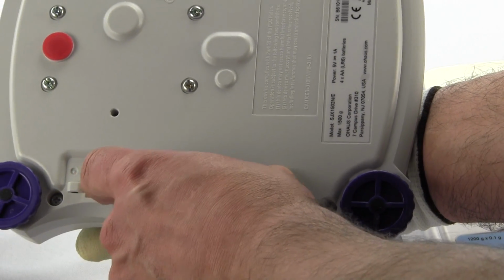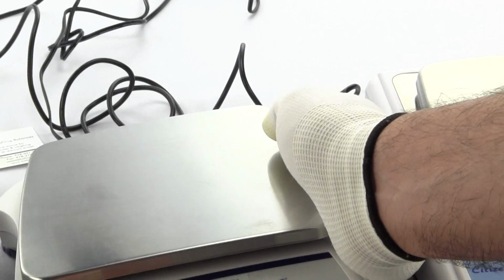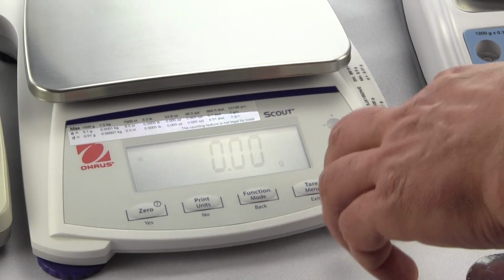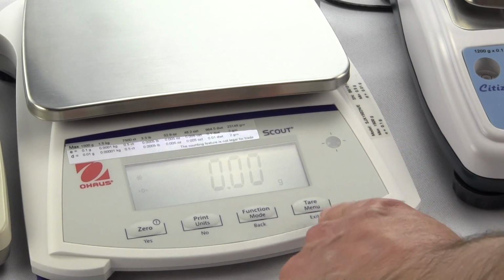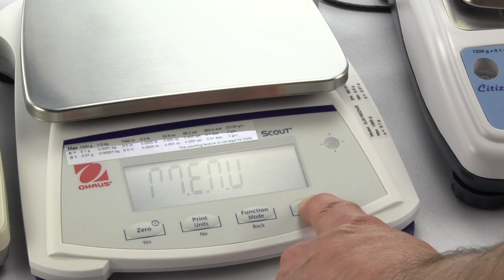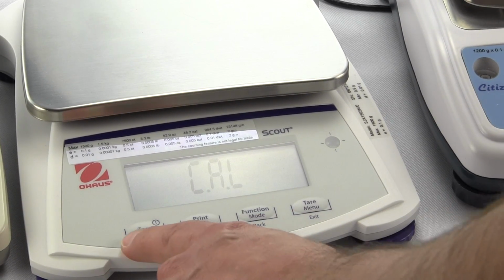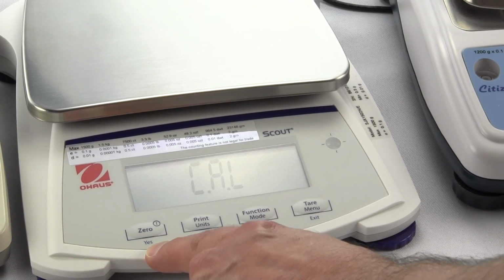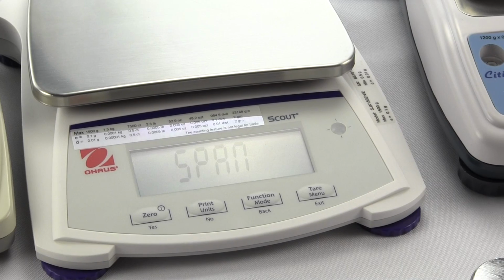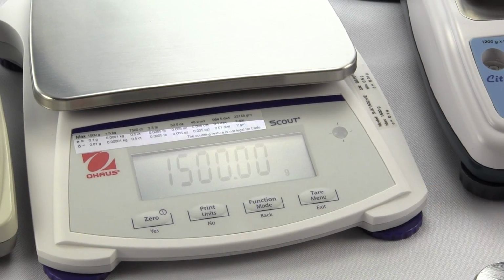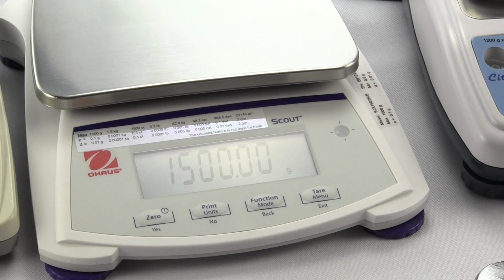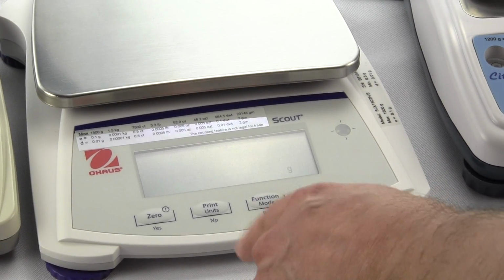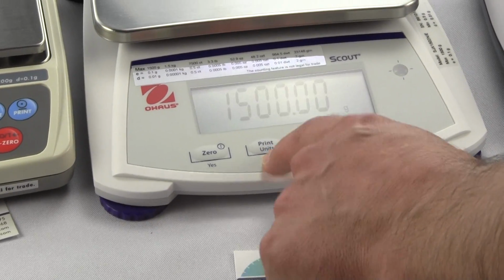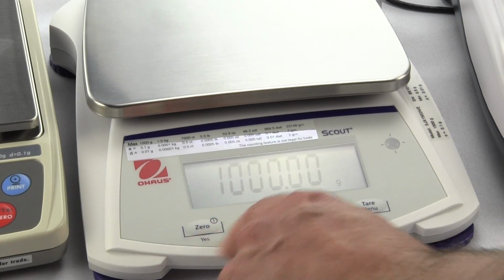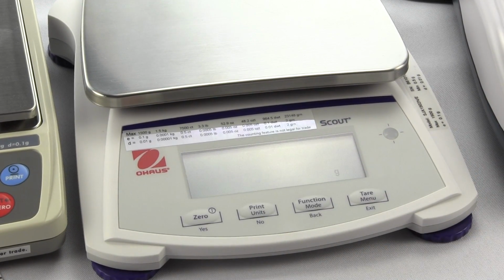So if I move it like that, it's still not going to work. I have to hear it click. When you hear that click, it's unlocked. Okay, and you'll notice when it's unlocked, the last decimal place is no longer bracketed. To perform a calibration, press and hold down the menu key, then release, you'll see cal. Then you want to hit this key here that says yes all the way to the left, press it once, it says span calibration, that's what we want to do. Hit enter, it says 1500 grams. On this unit, it's user selectable, either 1500 or 1000. I said I wanted to do it for 1000, so I hit no. It shows 1500. I'm sorry, it shows 1000. Hit yes.